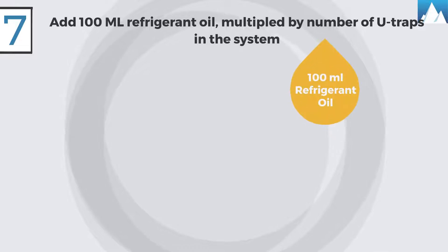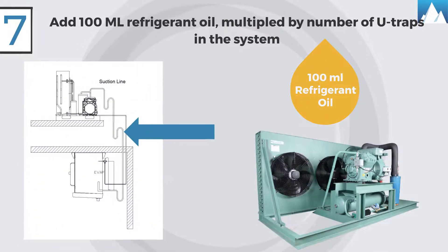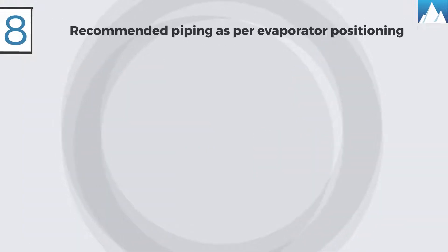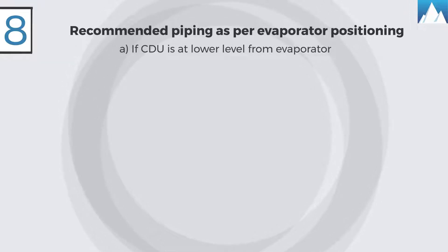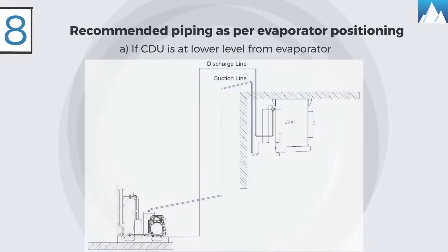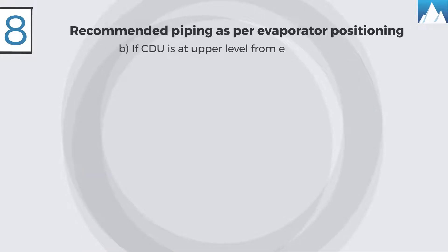Six, pressurize and leak test the entire refrigeration system including the condensing unit, evaporator, all connected tubing and fittings. Seven, add 100 ml of refrigerant oil in the system multiplied by the number of U-traps given in the interconnected piping. Eight, recommended piping as per evaporator positioning: A, if the condensing unit is at a lower level from the evaporator, give one U-trap on the suction line immediately coming out from the evaporator.